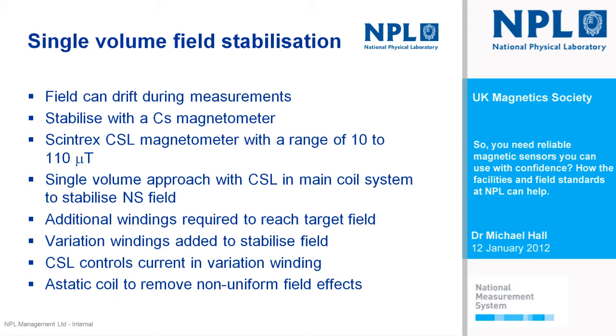And because there could well be a variation in the magnetic field within the coil system, because it's not perfectly uniform, we were using an astatic coil to compensate for that. And it's worth mentioning at this point that one of the major advantages of this approach of having your stabilizing magnetometer in the coil system is that gradients that occur between your reference magnetometer and your environment that you wish to have cancelled field in are a limiting factor on the performance that you achieve.